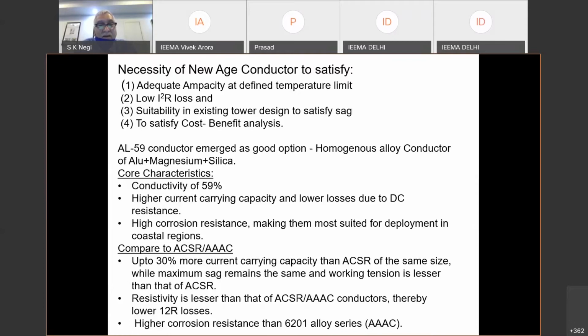This is the one paramount factor which I already said that drives the usage of conductor in an existing tower or a new tower you design. To satisfy cost benefit analysis is also equally important when you go to the board and to the decision makers, then they ask for cost benefit analysis when you are incurring additional cost. So in this situation, AL59 conductor emerged as a good option.